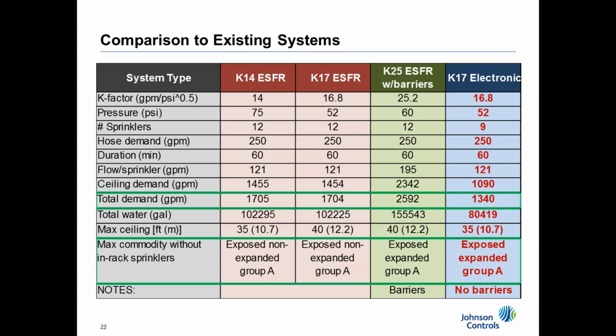So if you have applications where the building already has an ESFR system in it, but you want to increase your capabilities of what or who can store in that facility, in most cases you'd probably be able to do it with your existing piping system, changing out the heads, putting in electronic sensors, and running the electrical component to it, and not have to change out fire pumps or add additional water supply tanks to your facilities. And this actually allows for up to exposed expanded plastics with no vertical barriers. If you wanted to keep vertical barriers and go to a K25, which is a prescriptive code by NFPA 13, you can do that, but you're going to flow double the water requirements that you would normally have.